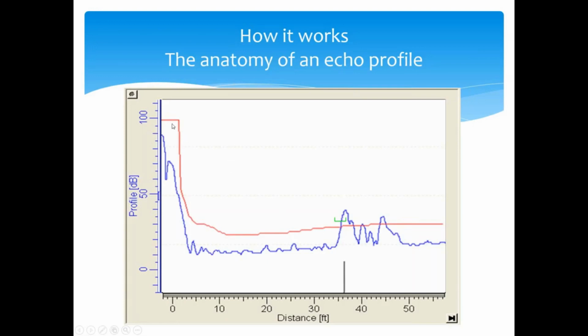And then my red line here is a threshold value. In our case, with Siemens, that is a dynamic threshold, so it changes over time, and we'll talk about that a little bit more. But as process conditions change within your tank, this threshold might slide up or slide down as your signal returns get higher in amplitude or lower in amplitude.